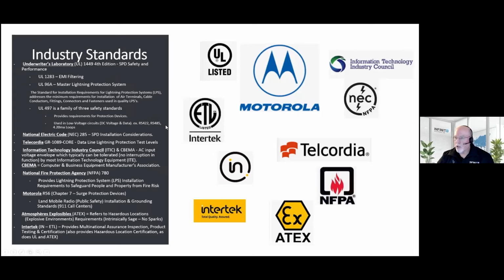But the one thing I wanted to show you here is Underwriters Laboratories. UL 1449, 4th edition, is the latest edition, and it is the standard for surge protection devices. UL 1283 is about EMI filtering, so if the surge arrestor has that requirement, it needs to have that capacitive inductive filtering network built into it. And this 96A is kind of nebulous, but I put the definition here for you. UL 497 is a standard for DC protectors and data protectors, so you'll see that for those.